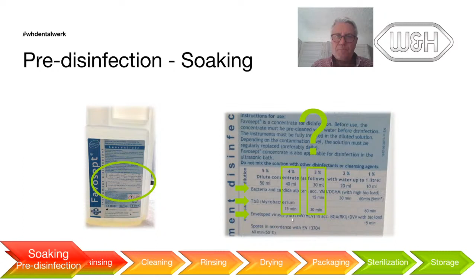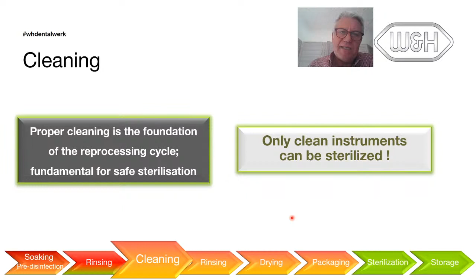Then you rinse and then you clean. Cleaning is fundamental. In many guidelines it says only clean instruments can be sterilized or sterile. And therefore here we don't need a disinfectant, we need a detergent, totally different properties, because detergents have cleaning properties. It goes from wetting and foaming. It will nicely wet, humidify, distribute the detergent onto the surface of your instruments. It will emulsify, so it will remove stains, debris, dirt from the surface and prevent this from coming back onto the surface. So it's called dispersant.